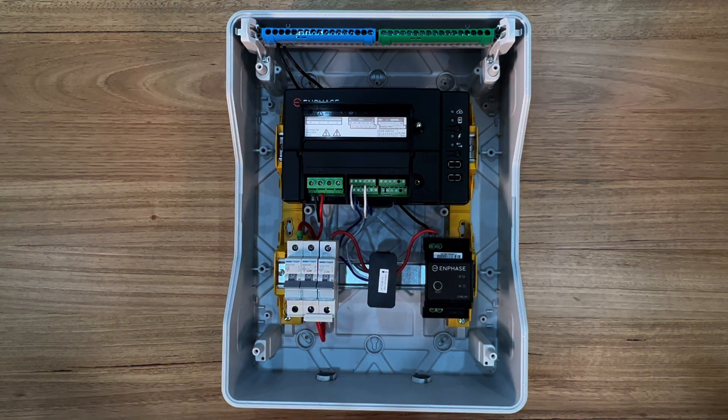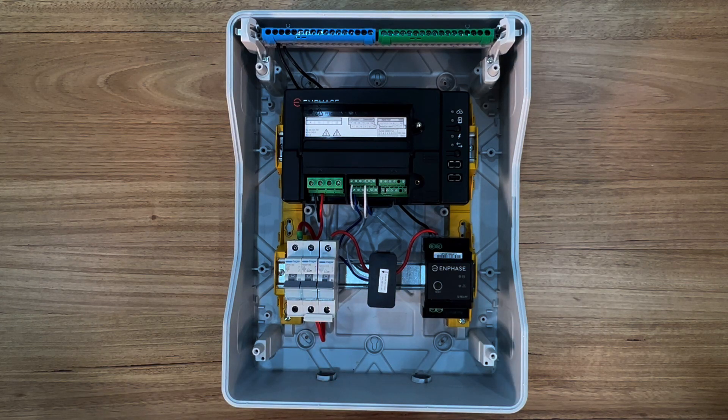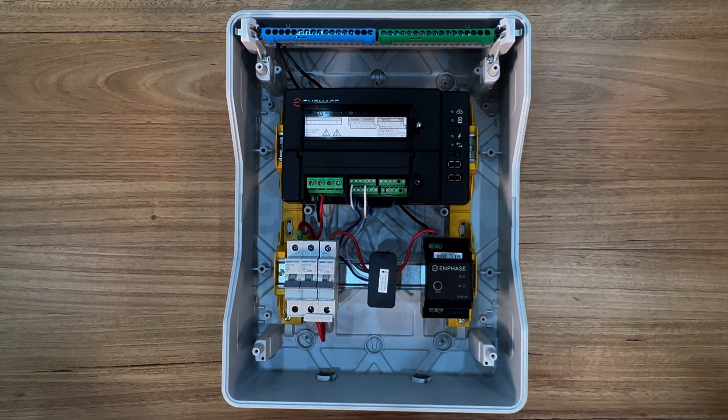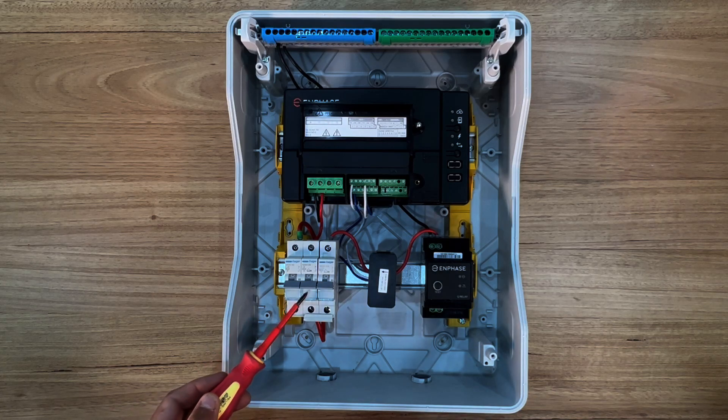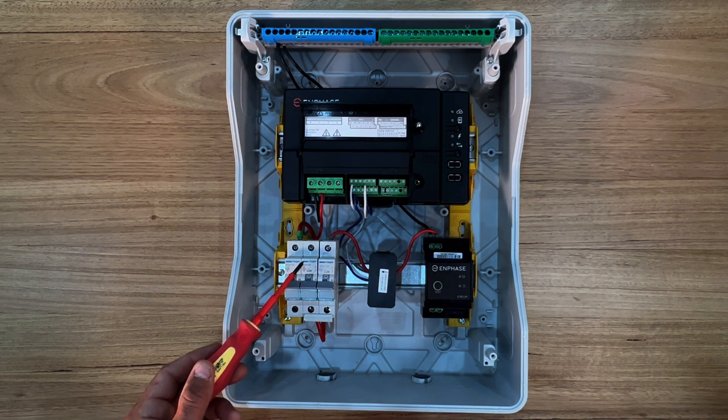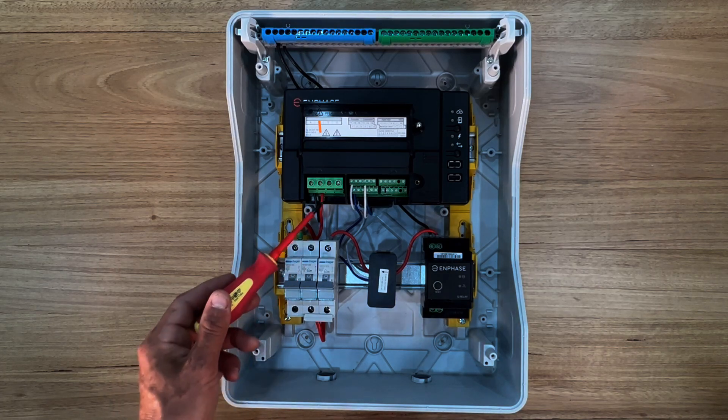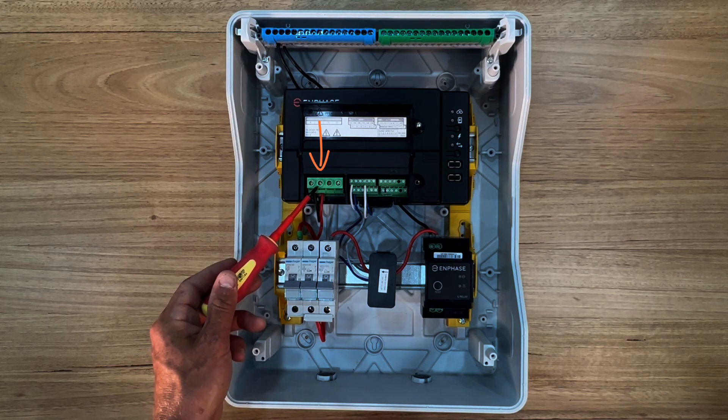An IQ gateway is 12 modules wide and mounts directly to the DIN rail. In this example it is supplied from a 6 amp circuit breaker. Note that the active conductor connects to the L1 terminal here.